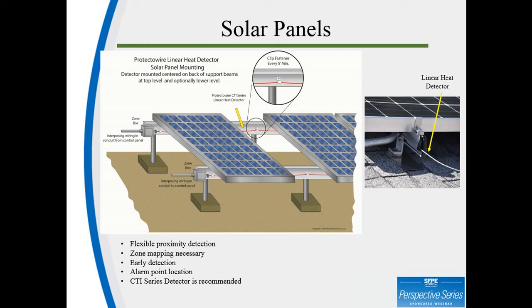Protecting solar panels is the second new application where we have seen significant activity. While solar panels themselves rarely fail, external environmental factors have a significant impact on the reliability of solar panel arrays. Whether it's age, maintenance operations, roof debris, animal nests, poor electrical work, or physical damage, the panels can overheat. For this application, the linear heat detector is typically placed on the highest longitudinal support beam, as you can see in the illustration on the left side of your screen.